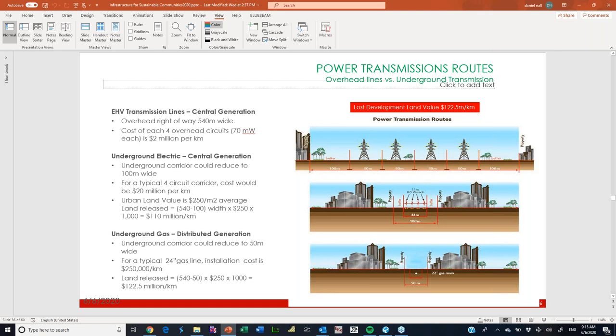So we did a land use study for the various alternatives. We had our extreme high voltage transmission lines with central generation. The overhead right of way required for these very high transmission towers into the city was approximately 540 meters wide. The cost of each of the four overhead circuits, 70 megawatts each, was $2 million per kilometer.